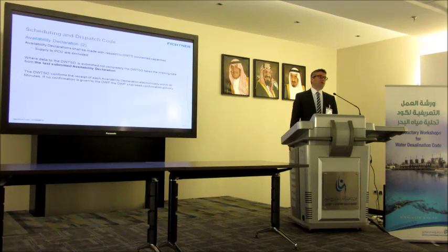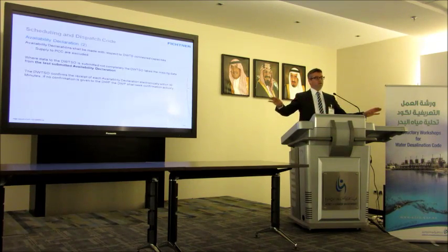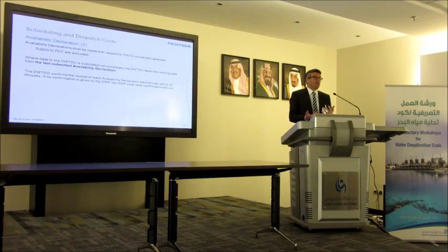It needs to be considered that any plant-connected consumers, any capacity or flow of water volume to plant-connected consumers needs to be subtracted. Otherwise, the TSO would think that such plant, which provides water to the transmission system and plant connected consumers, would have more capacity available than it actually has.